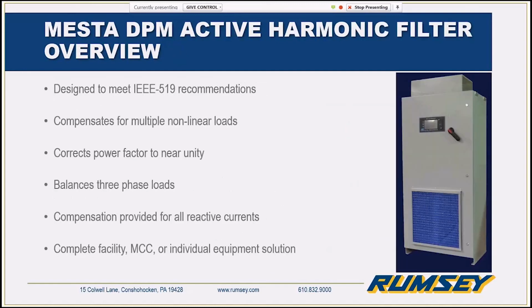So what can an active filter do for you? If you're not familiar with active filters, we're designed, again, to meet those IEEE 519 recommendations, meet that strictest standard of 5%. The biggest differentiator between us and other harmonic mitigation techniques is that we can correct for any number of loads downstream of us. So one active filter on a lineup could take care of a whole MCC or potentially take care of a whole facility. In addition to correcting for harmonic distortion, we can correct for the power factor as well, and we can balance the three phases. And I'll talk to you a little bit about the relationship between being able to correct for all of those at once and some of the cost savings that they provide.